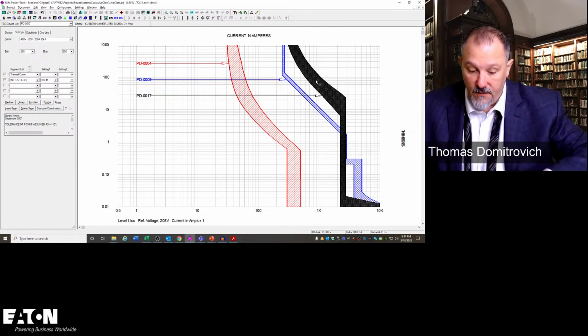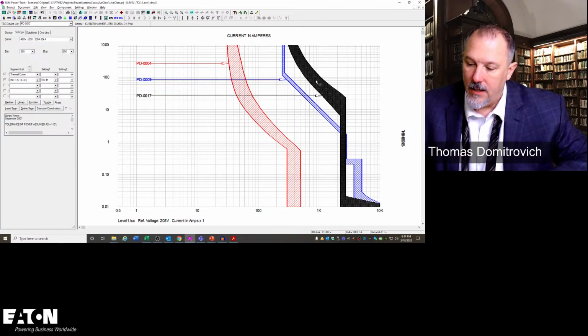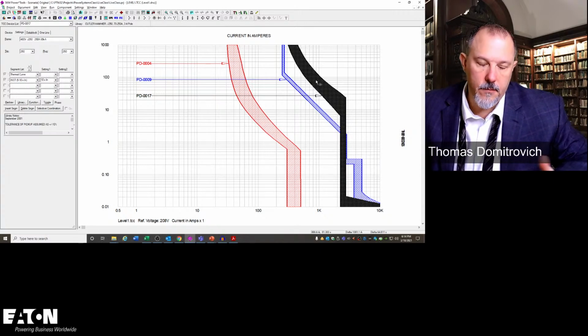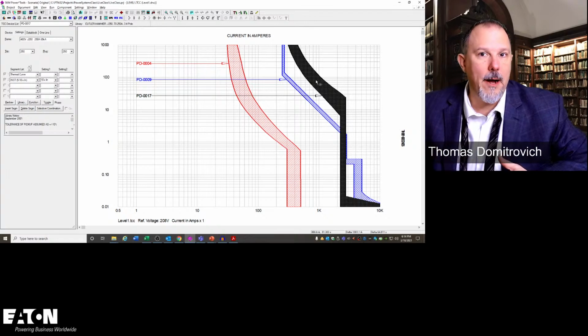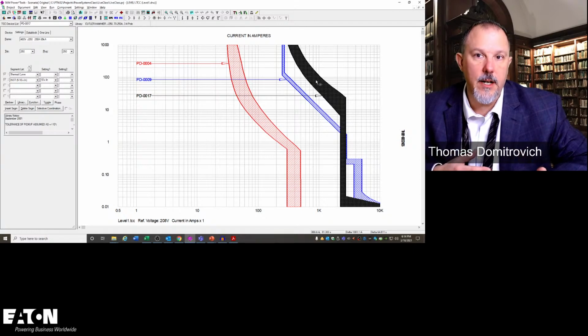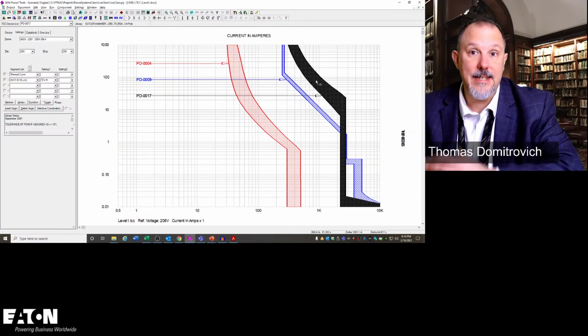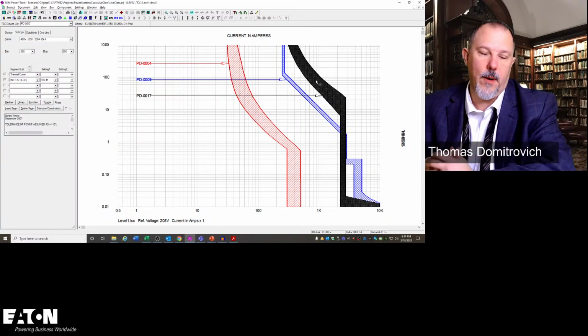I could feel comfortable saying, look, the likelihood of you getting a three-phase bolted fault current is low. Granted. And I took steps. I'm not required to go to the three-phase bolted fault current, but I know ignoring fault current is not a good thing either. So I went to a ground fault current, advised my customer of that. They said thumbs up, and that's what we went with.